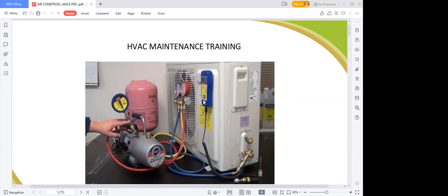And the work of the condenser is to discharge the hot temperature out. That's why you see your vendors, even sometimes some of us will dry clothes in front of the AC, because heat is coming out of it. So when it pushes out that temperature, the next stage is for the pressure to go down. And what handles that pressure is your expansion valve. Once the expansion valve takes care of the pressure, it now acquires the refrigerating effect, which I call the cooling effect. And the last stage for the cooling to get to you is your evaporator.